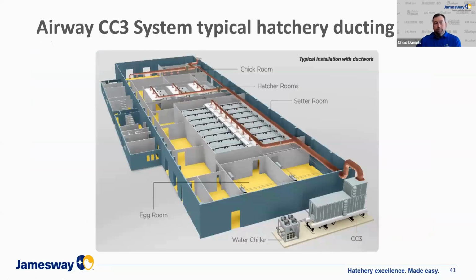And again, the ducting on a unit like this is a little bit similar to the modular, but you only have one supply. So in this case, the discharge air temperature is controlled specific to generally incubation rooms, but where that supply duct goes on to hatcher rooms, you'll see a supplemental heating cooling coil in this duct. Same for chick rooms, where those rooms could be controlled to a lower temperature to satisfy the needs for those rooms.